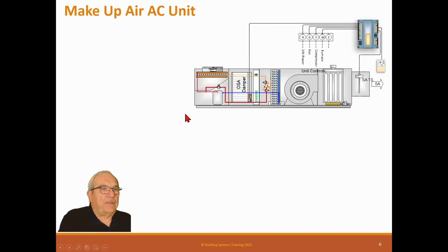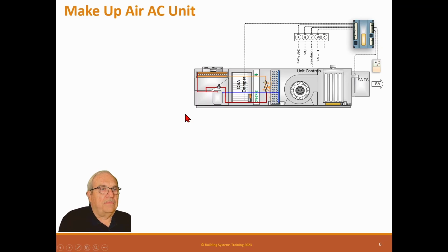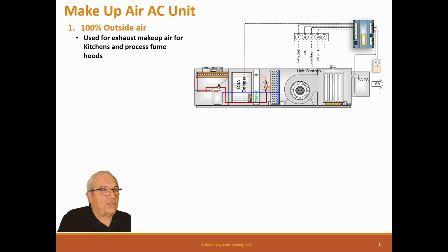Okay, here's a makeup air AC unit. Now this is a 100% makeup air unit. It's just an AC unit. So it has to be sized for an environment that can handle this. So basically it's a 100% outside air unit used for exhaust makeup air for kitchens and process fume hoods. DX refrigeration will only perform with ambient temperatures below 100 degrees.